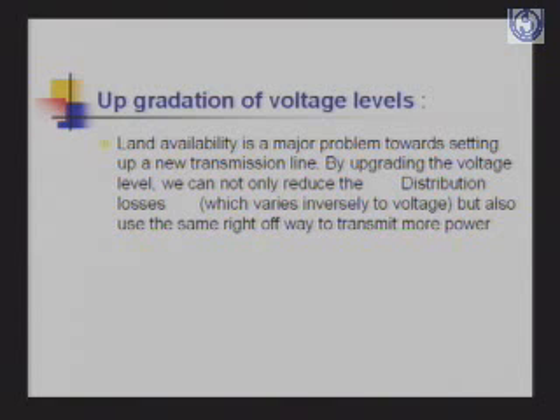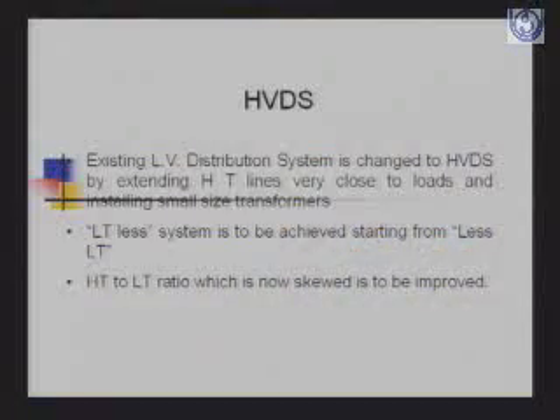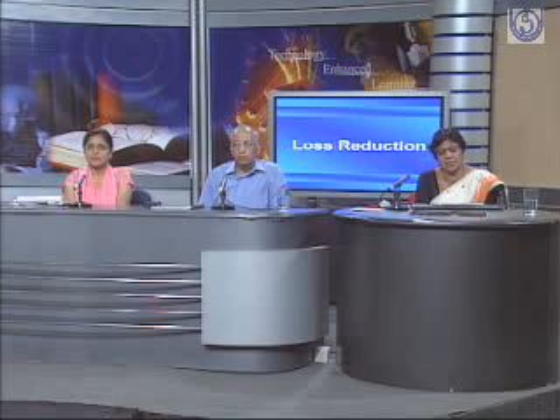So for this we need to upgrade our voltage levels. We have a low voltage distribution system, as we discussed, in which the capacity of the transformer is high and we take long LT lines. But by upgrading the voltage level, we take the distribution at 11 kV and make the size of the transformer smaller, then it becomes a high voltage distribution system. So the high voltage distribution system is a method of increasing the HT and reducing the LT. The existing LV distribution system is changed to a high voltage distribution system by extending the HT line very close to loads and installing small size transformers. An LT-less system is to be achieved, but we start from less LT.